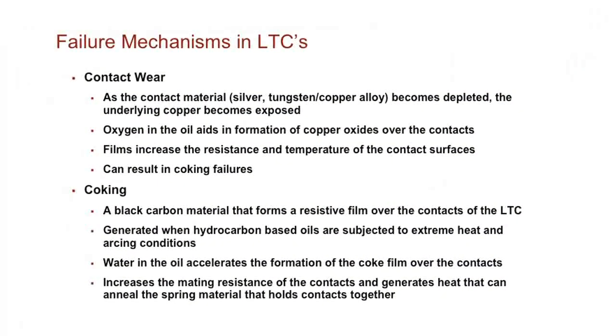Part of what happens is you have the oxygen in the oil, which basically aids in the formation of what we call copper oxides. And the copper oxides basically form a film creation on the contact surfaces of the LTC. And that's how you get into your coking issues, which your contact, the film starts building up, your contacts are not making 100% as they're sliding back over, so therefore you get into what we call coking effect, which is just a black carbon buildup on the contact surface itself. It's a normal thing that happens in tap changers. It happens in almost all tap changers.